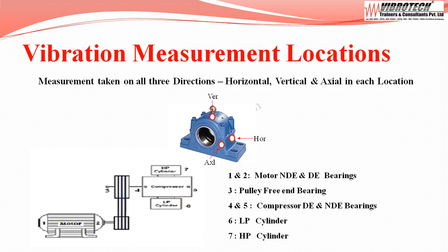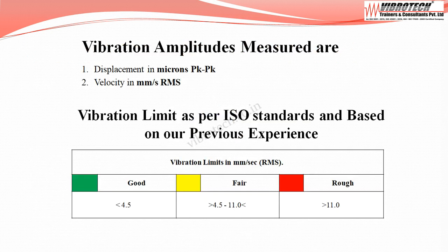Vibration measurements are taken in all three directions: horizontal, vertical, and axial, at each location. Measurement locations are: motor non-drive end and drive end bearings, pulley free end bearing, compressor drive end and non-drive end bearings, low pressure cylinder, and high pressure cylinder. Vibration amplitudes collected are displacement in microns peak to peak, and velocity in millimeters per second rms.